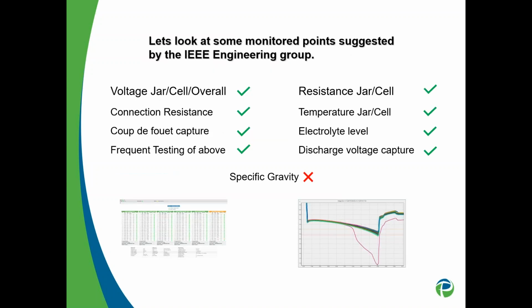Some of the things in there are going to be voltage, per jar, or cell, or even string voltage. You want to grab that measurement, the connection resistance, the coup de fouet. You want to see when that discharge happens, if it's snapping back, that whiplash effect you get after a discharge.